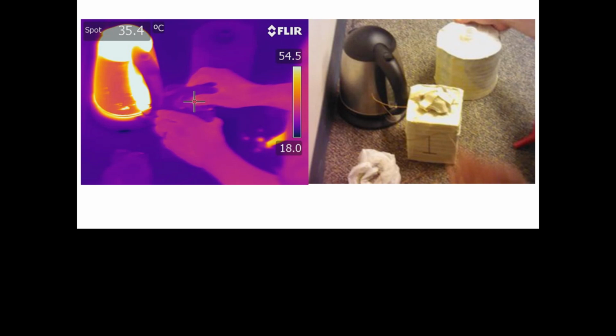So, and here, this is plastic, right? It's close to 1. So this would be like 0.1, and this is 1. And guess what? Now this plastic is emitting radiation like crazy. And the dumb camera says, oh man, this has to be real hot. So part of the catch of all these things is you gotta know how to interpret these things. It's pretty, but prettiness takes you only so far.